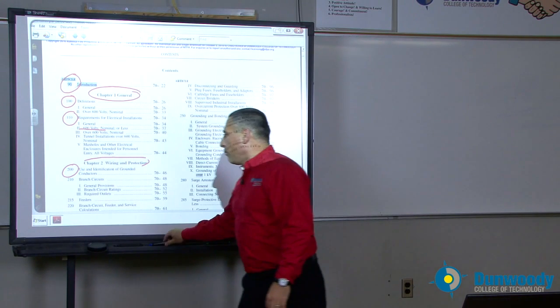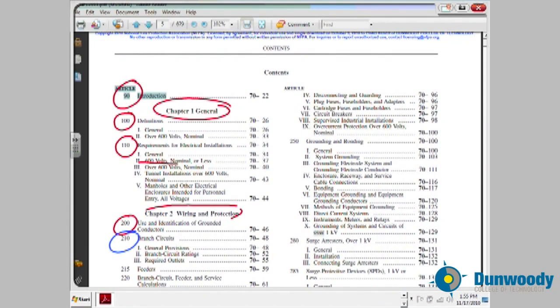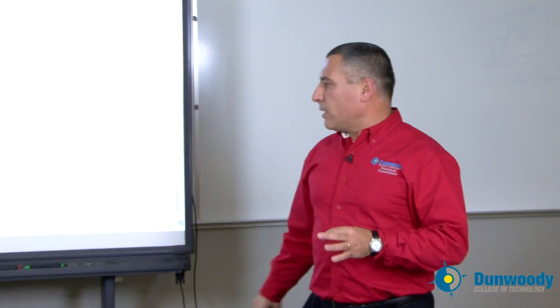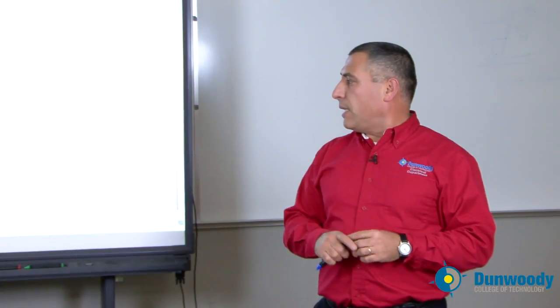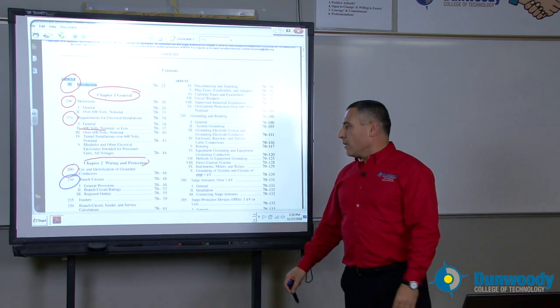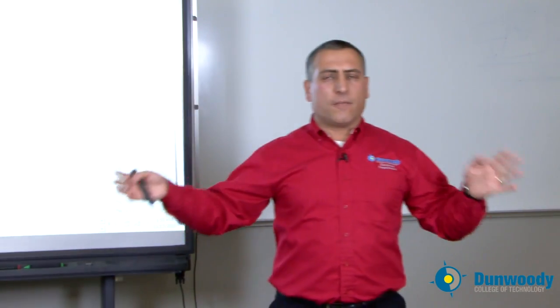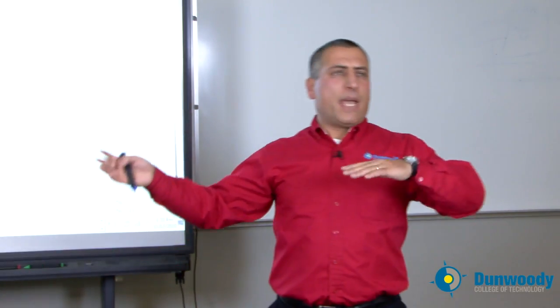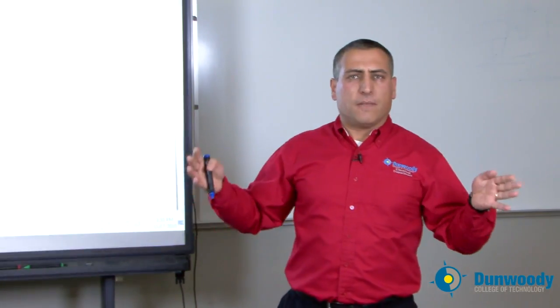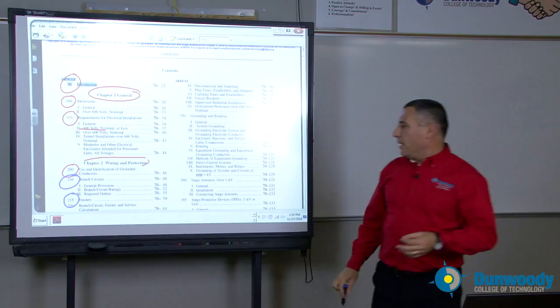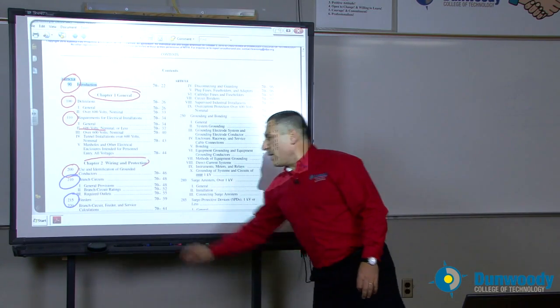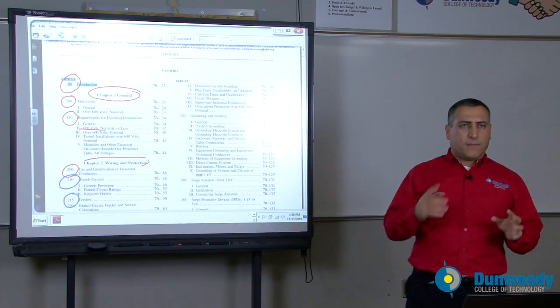Then we move into branch circuits, which are extremely important for lighting, receptacles, and dedicated circuits. What is the largest branch circuit you can pull out of a panel? All this information is found in Article 210. Article 215 talks about feeders — conductors and conduits between two panels, for example bringing power from a 4,000-amp panel A into a 2,000-amp panel B. How do you size a feeder and protect it with an overcurrent protection device? These are very important topics.